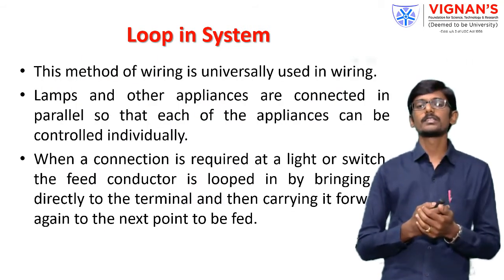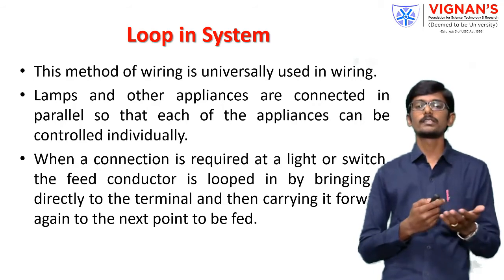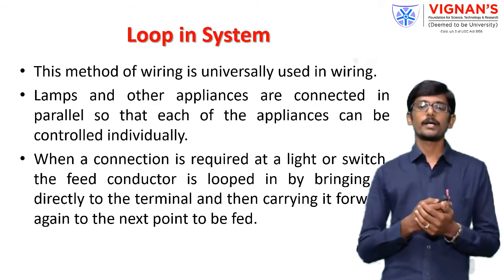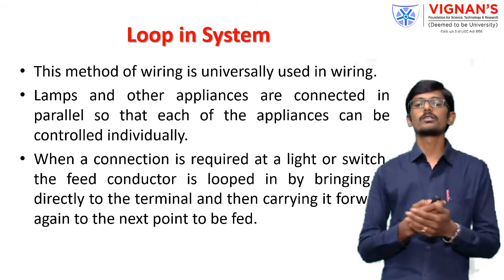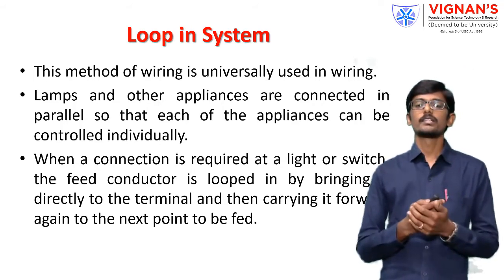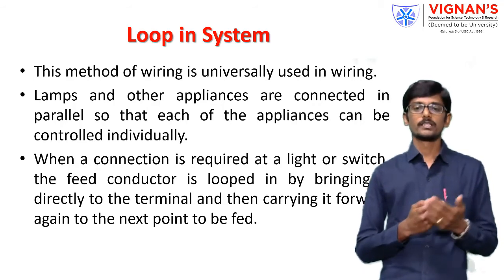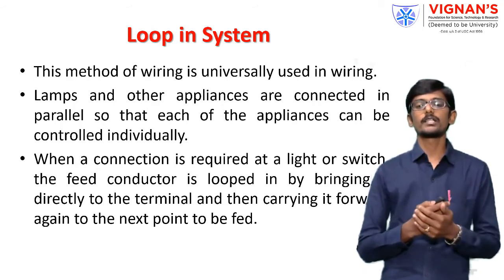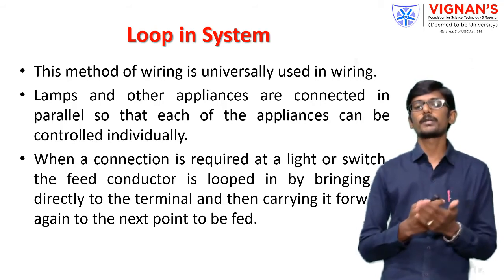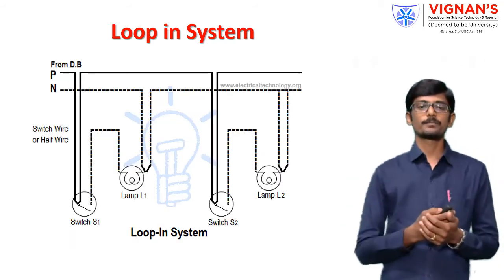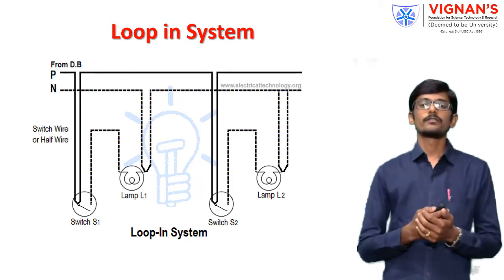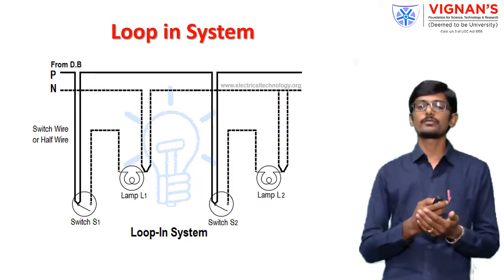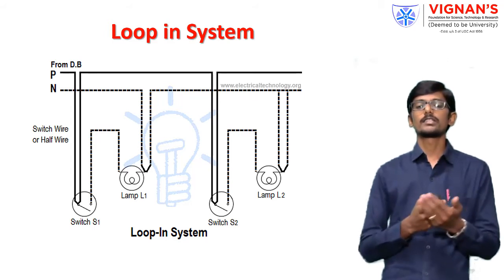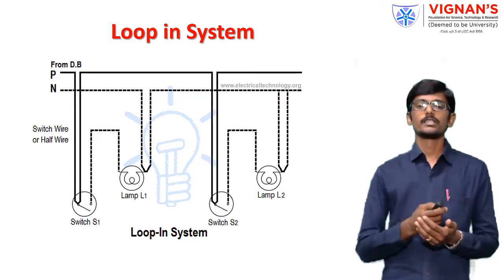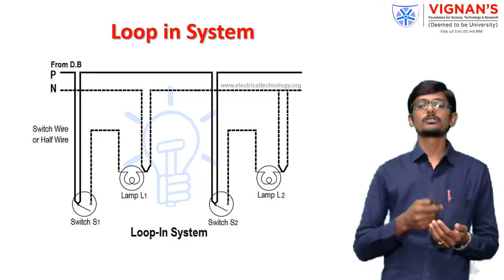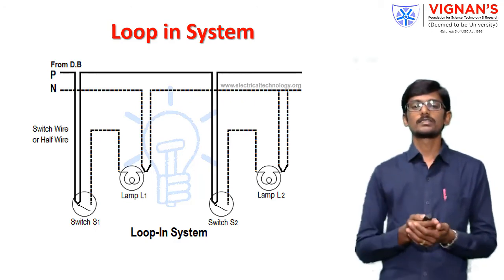And the loop-in system is universally used wiring. The lamps and other appliances are connected in parallel, so that each of the appliances can be controlled individually. When a connection is required at a light or a switch, the feeder conductor is looped in by bringing it directly to the terminal and then carrying it forward again to the next point to be fed. This figure shows the loop-in system wiring, where the phase connection is given to switch 1, and from switch 1 we take a connection to switch 2. The wiring will flow from one part to another part through the appliances. This is called the loop-in system.